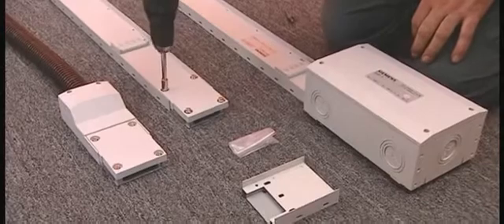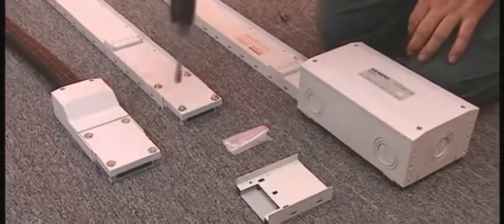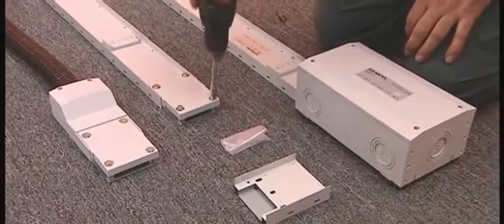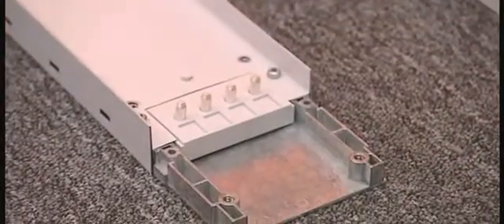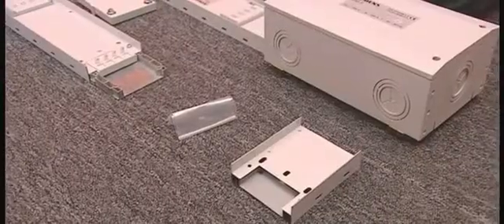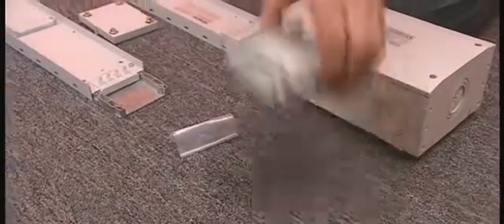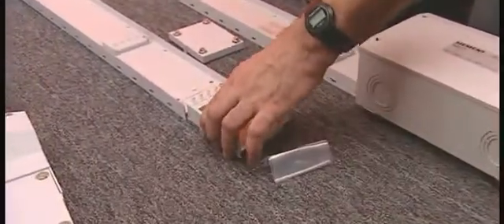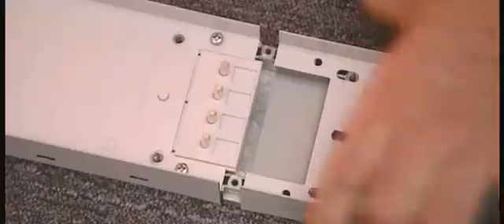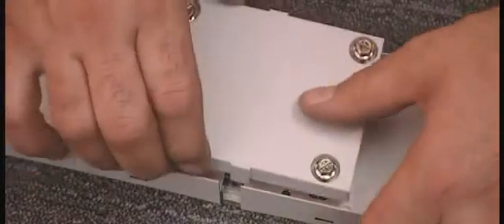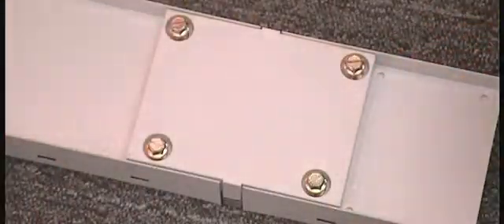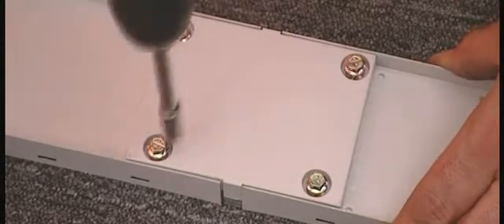The cover of the last trunking unit in the bus bar is opened. The clamp terminal is removed. The last trunking unit is now equipped with the second end flange. The clamp terminal is replaced on the trunking unit and secured as a connector.